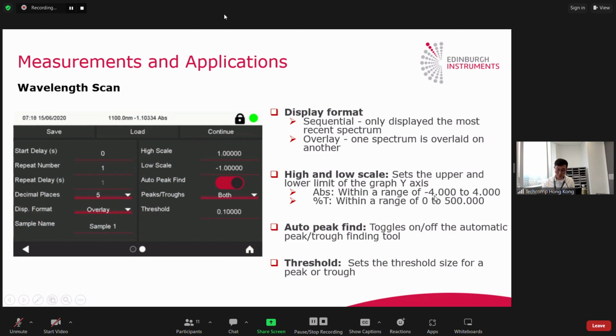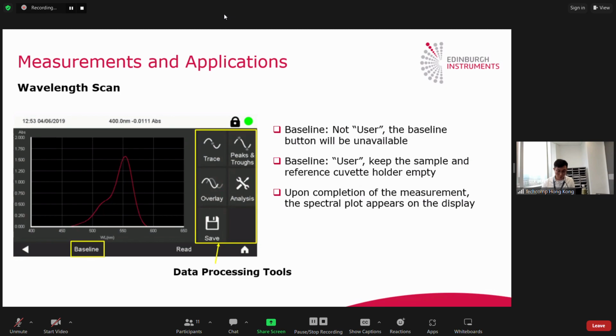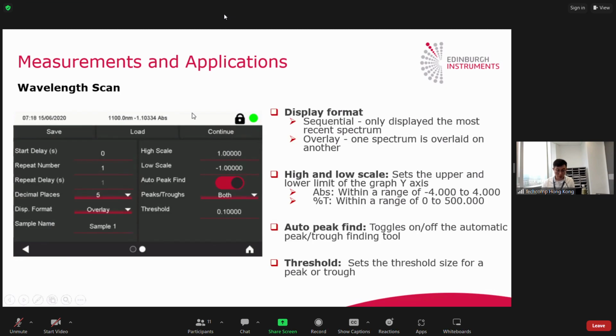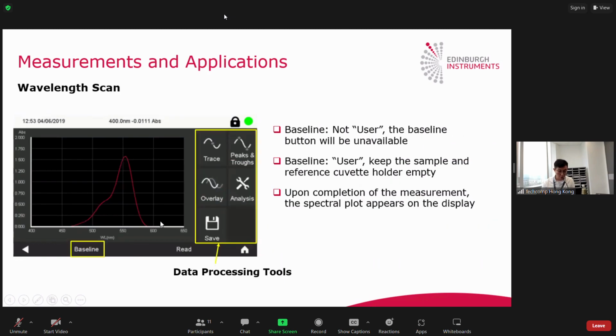The range is set here, and you can choose to automatically find the peak, or you can modify the threshold of your peak finding here. After you press the continue button, you will enter this screen. When the baseline is not set to user, the baseline button here will not be available. When you choose the baseline as user, you can use an empty sample and reference cuvette to measure the baseline.